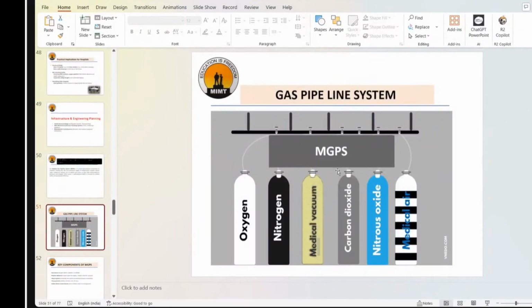So these are some colors you must know. These are the important things. And during the assessment or the inspection of the NABH, we used to check the color. जैसे oxygen का, you must remember its pipeline color is white and medical vacuum का yellow. These two basic colors you must remember. These are the most common colors which are being utilized in the hospital.